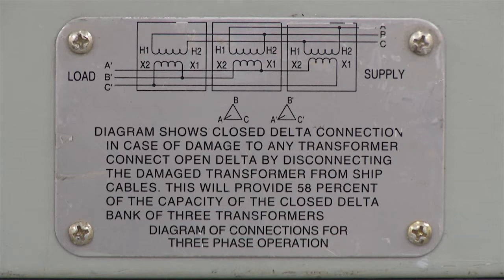This diagram shows a closed delta connection. In case of damage to any transformer, connect the open delta by disconnecting the damaged transformer from ship cables. This will provide 58% of the capacity of the closed delta bank of 3 transformers. The diagram shown is of connections for 3-phase operation.